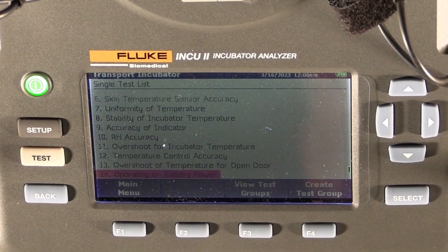And then number 14, we've got operating on battery power, where we disconnect the machine from AC power, leave it on battery power for at least half an hour, and see how constant our temperature stays within that half hour. That will tell us whether the batteries are able to keep the heaters and the fans running for that period of time.